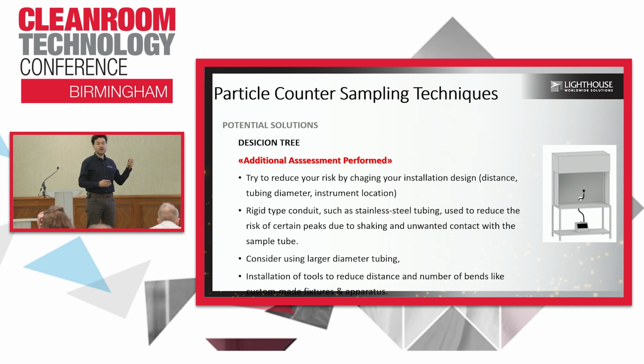This is the one I described at the beginning. Sometimes we are seeing very long tubing coming along the sample point, but whenever you touch this tubing, you see the peak. So instead, defining your certain radius as well as defining the certain path to sample using these stainless steel conduits is the best application. And again, using larger diameter tubing is important if you have this kind of risk.